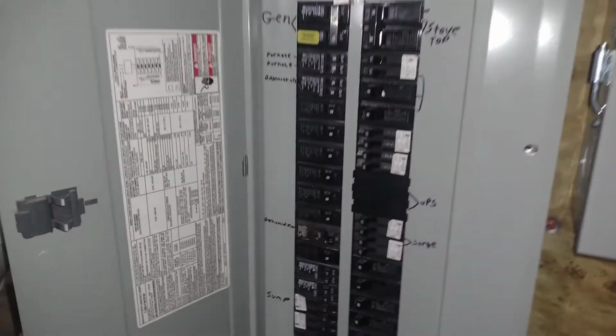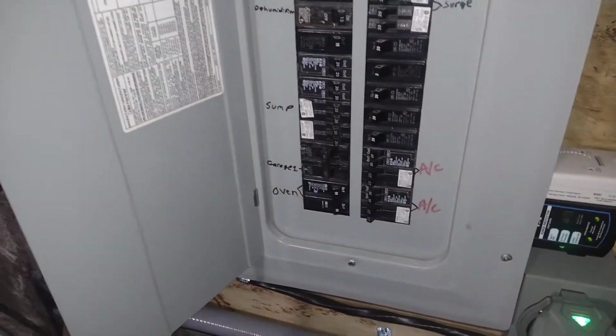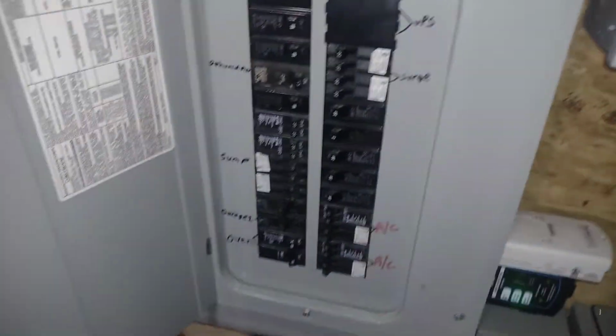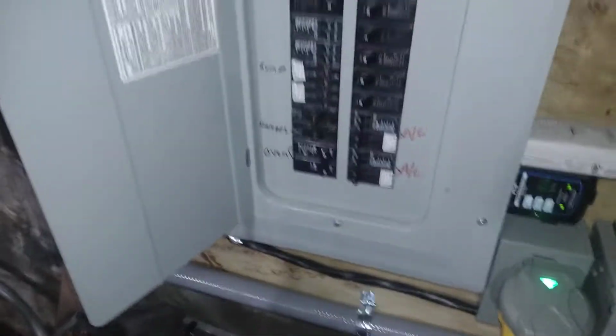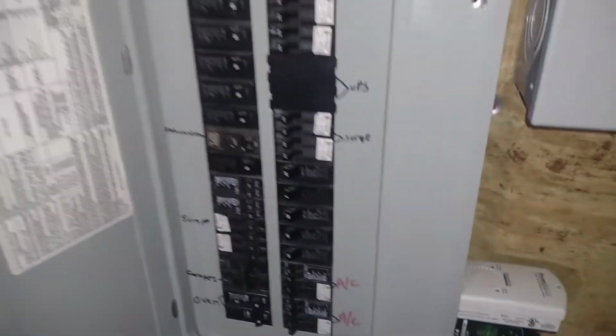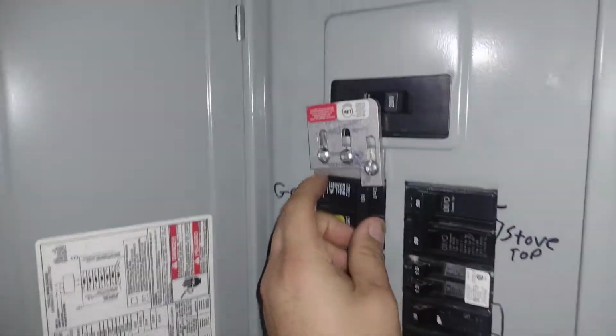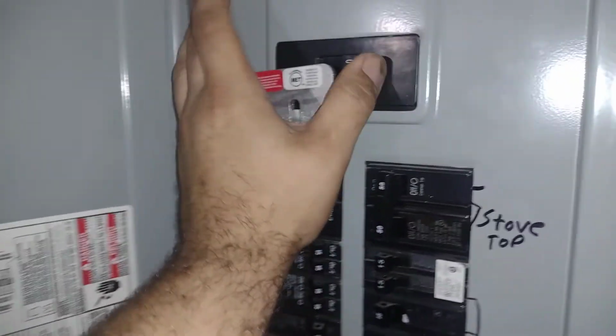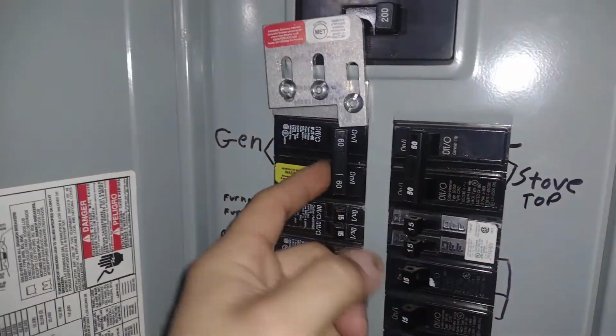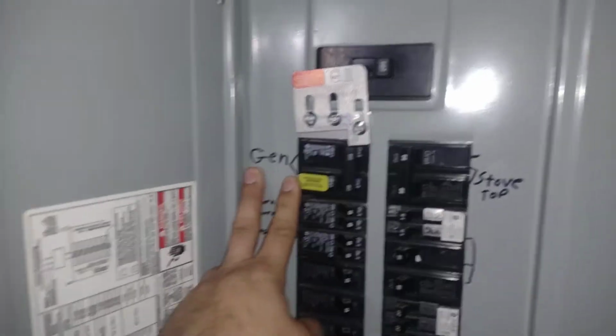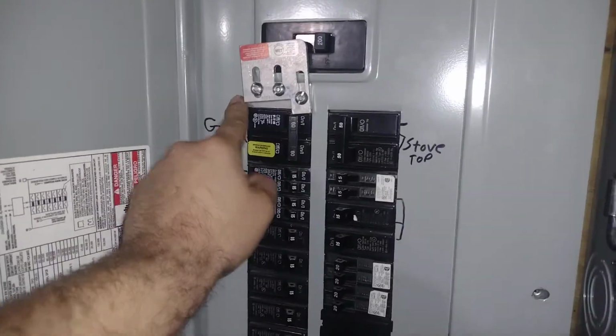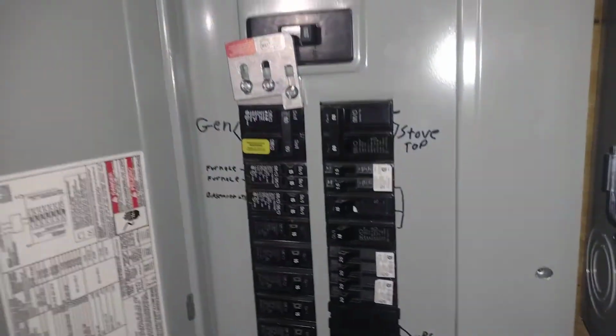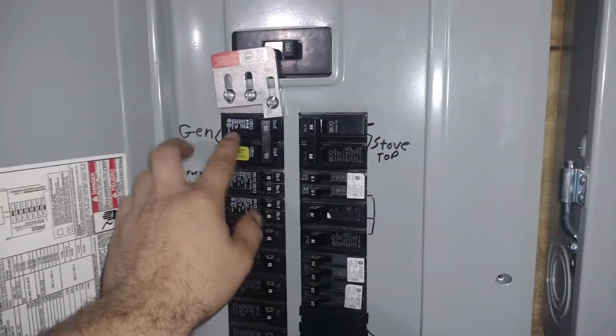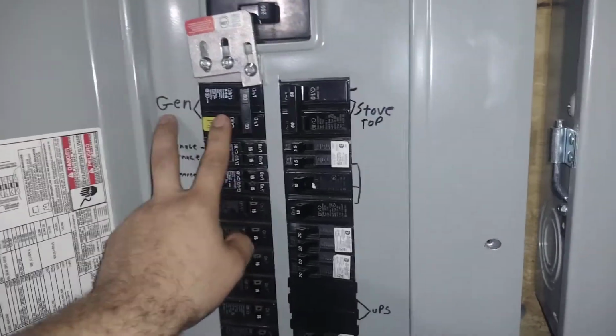We've got the main, what do we call this? The critical loads panel, even though it's literally everything except the air conditioners, which I pulled off here. It used to be down here, so I moved some stuff around. But there's the interlock switch, so you can't accidentally turn on the main while the generator's on, and vice versa. It's marked generator because that's the way it used to be, so now we'll just call it solar generator or diesel generator. And I can select how I want to power this breaker to feed the house with either the solar or the generator, or both at the same time.